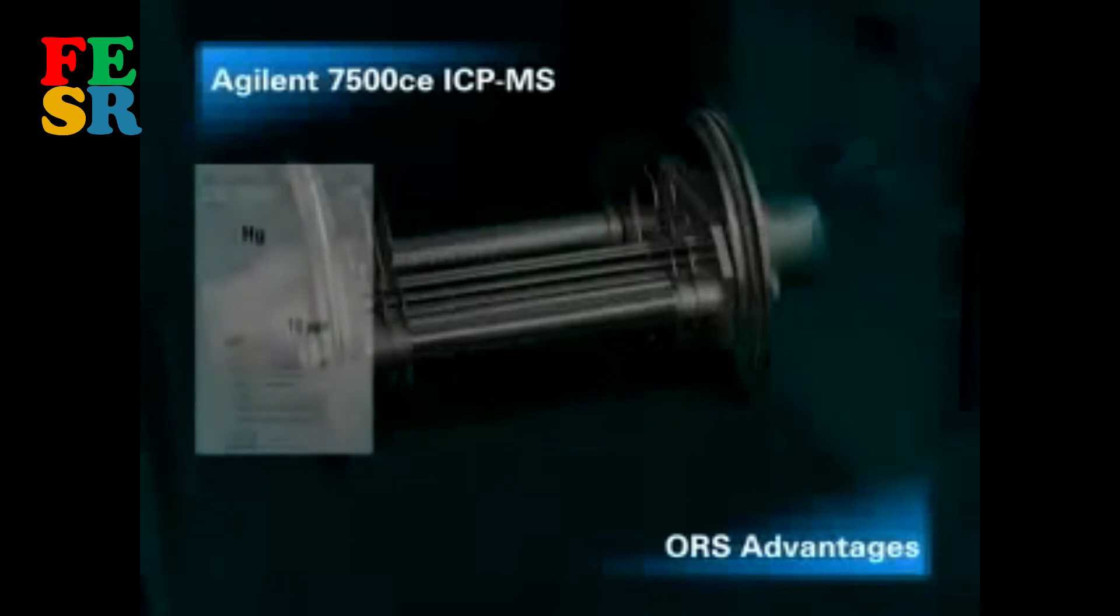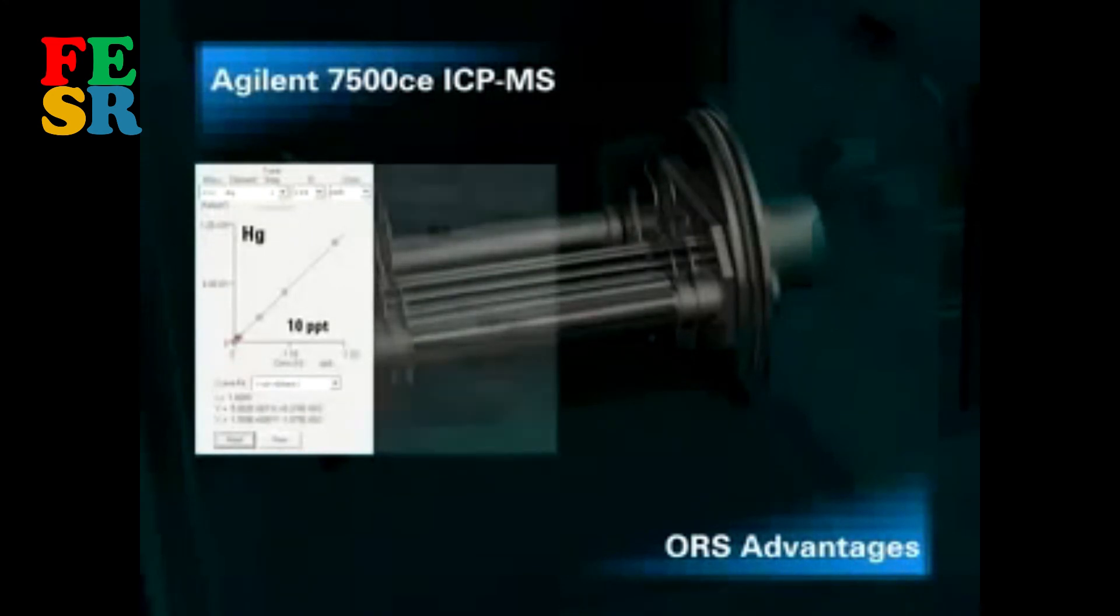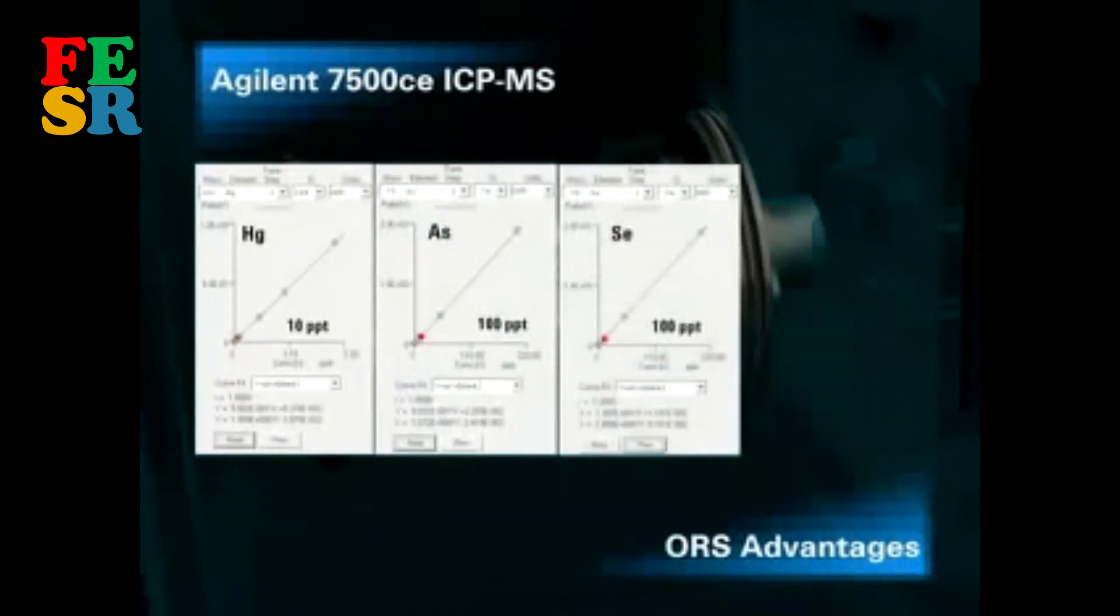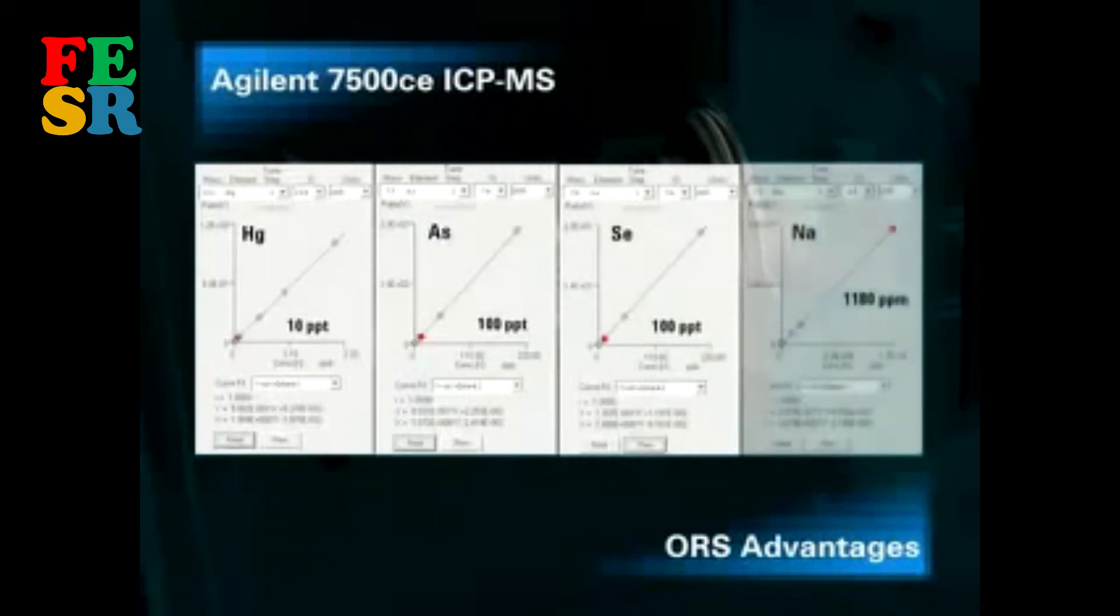The calibration graphs show excellent linearity for mercury down to the 10 parts-per-trillion level, arsenic and selenium down to 100 parts-per-trillion, and sodium at 1,180 parts-per-million, all achieved in the same run.